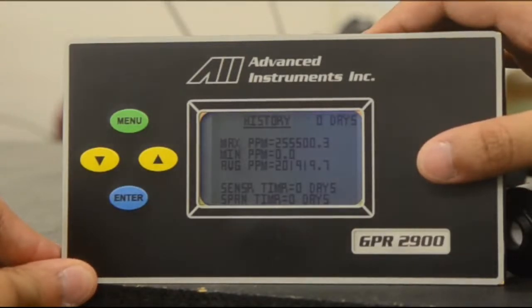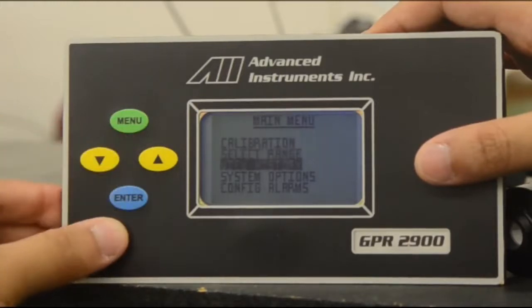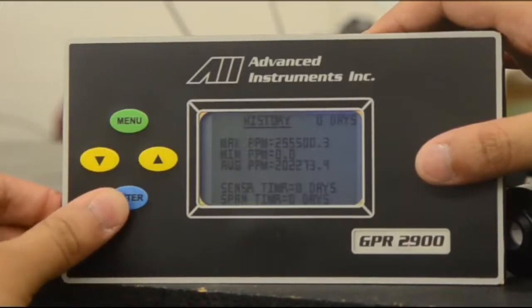Once a new sensor is installed, the value will be recorded of that sensor. You will see your max level, your minimum level, and your average level of oxygen when you first installed the sensor. Right now we have max at 25% roughly, and average at 20.1%. Again, that is scroll down to view history, press enter, and you are looking at this screen here.